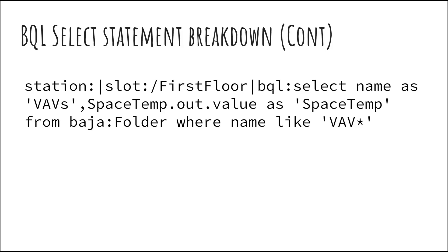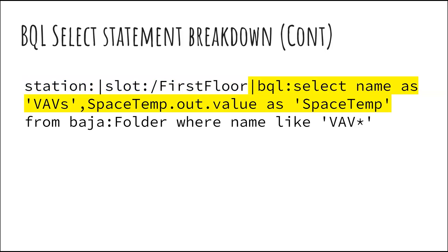I wanted to search from only folders instead of control points where the name was like VAV. Let's look at how this statement is broken down. The first part — station:slot first floor — is the base ORD being applied. The query is not going to return any components that are not children of the base ORD. Every BQL query starts with a base ORD followed by the BQL select. The following text defines what data we want to receive — in our case, name and space temp.out.value — used as our columns, resolved and populated by each result when we run our query.